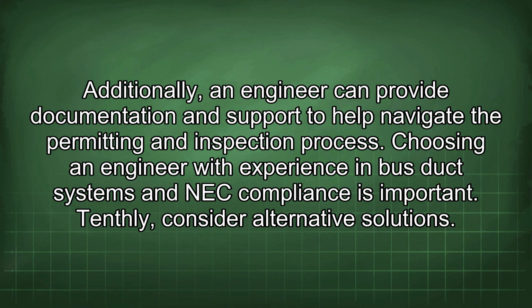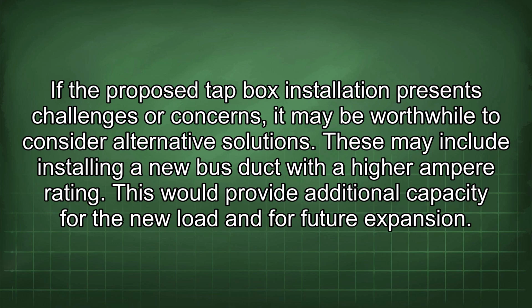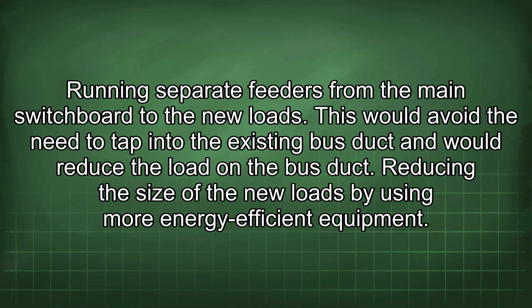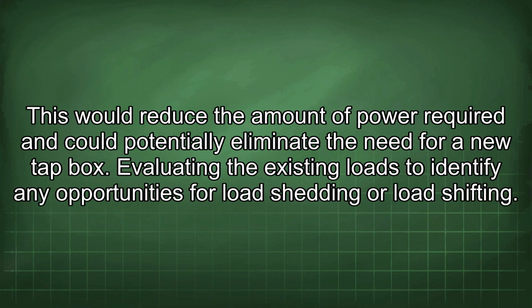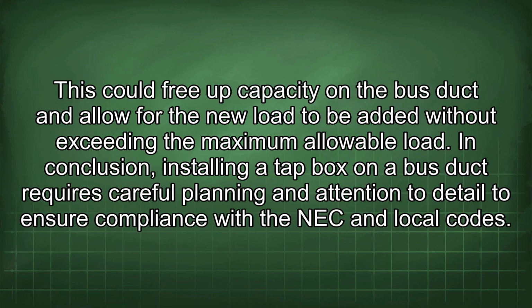Tenthly, consider alternative solutions. If the proposed tap box installation presents challenges or concerns, it may be worthwhile to consider alternative solutions. These may include installing a new bus duct with a higher ampere rating. This would provide additional capacity for the new load and for future expansion. Running separate feeders from the main switchboard to the new loads. This would avoid the need to tap into the existing bus duct and would reduce the load in the bus duct. Reducing the size of the new loads by using more energy-efficient equipment. This would reduce the amount of power required and could potentially eliminate the need for a new tap box. Evaluating the existing loads to identify any opportunities for load shedding or load shifting. This could free up capacity in the bus duct and allow for the new load to be added without exceeding the maximum allowable load.